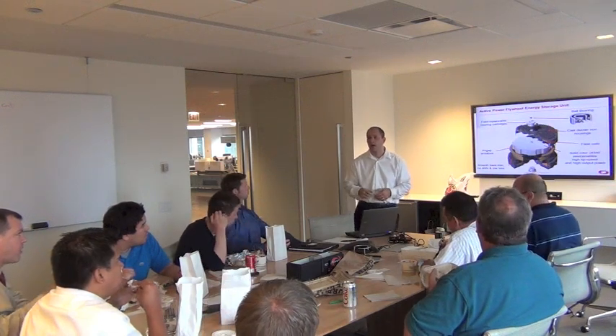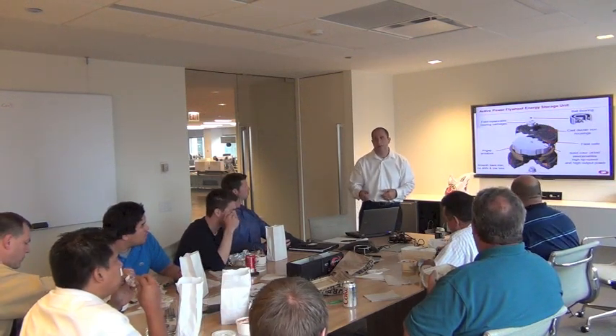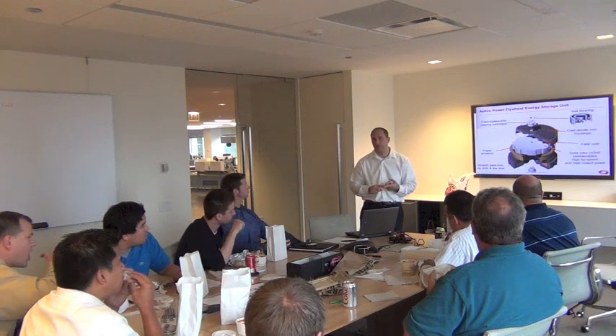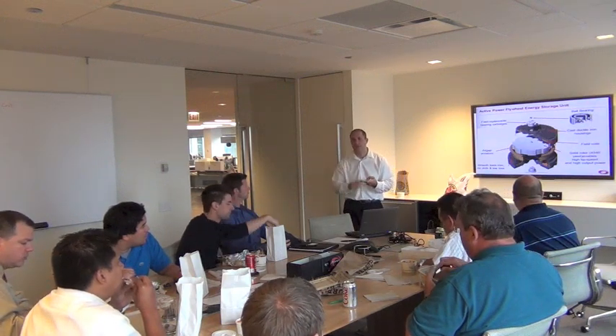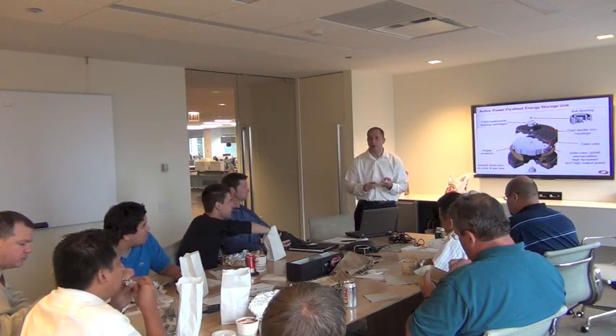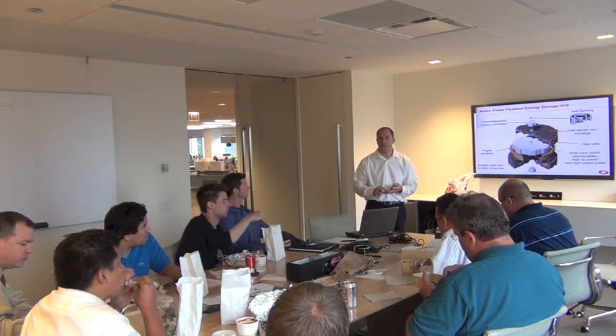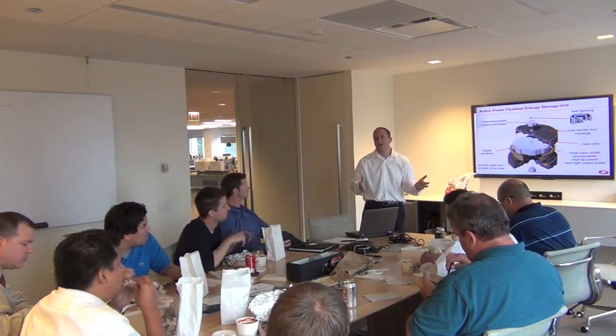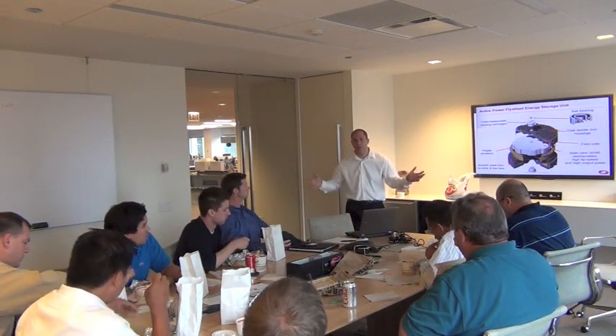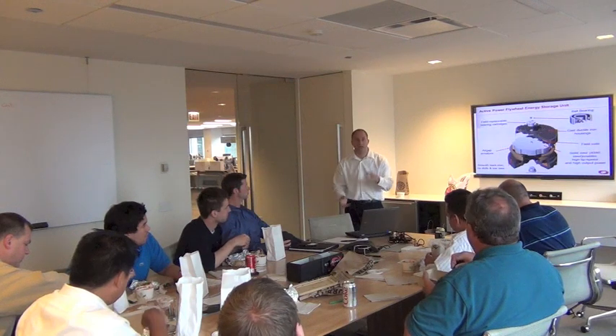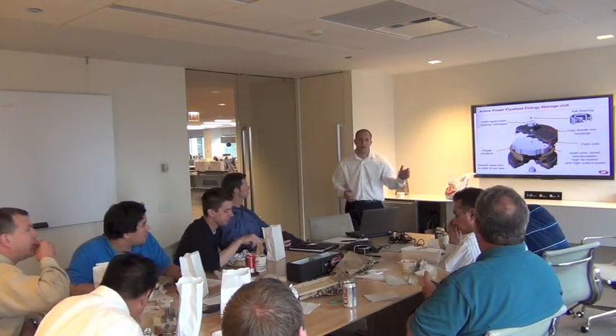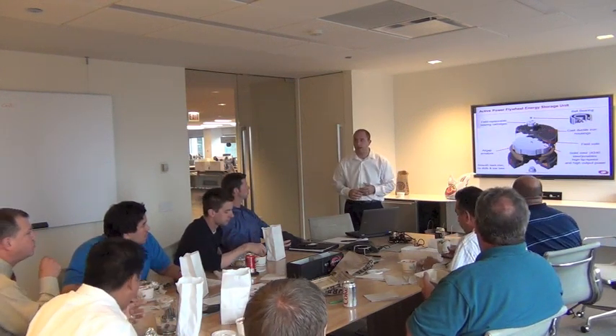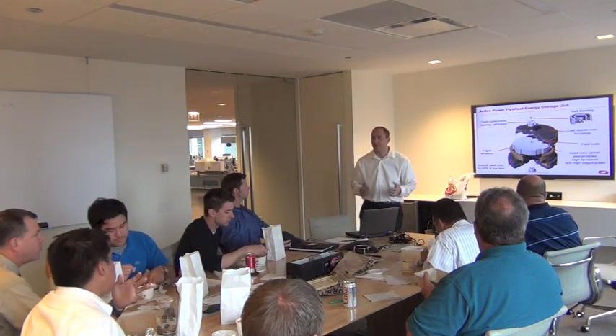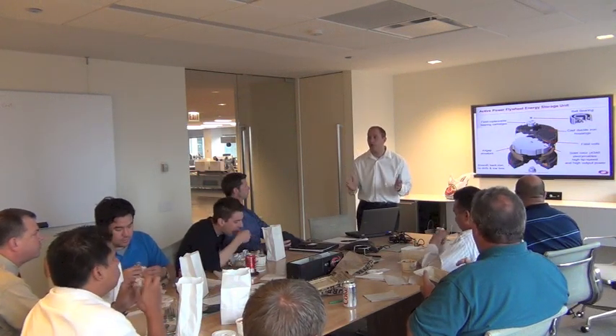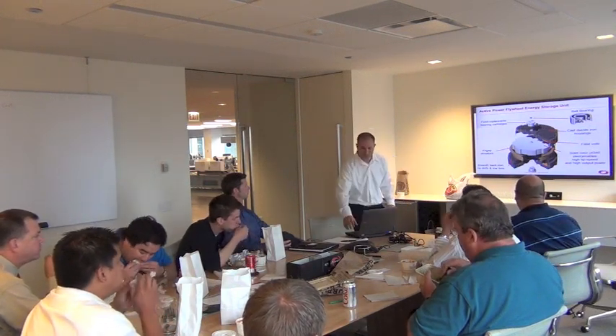You take the filters out. You can vacuum them out or clean them out or even wash them. Typically, that's just done once a year. So once a year, you'll clean the filters, change the mineral oil in the vacuum pump, and then once every 4 years, you'll change the bearings on the wheel. And when you have a multi-module installation or multiple wheels, you can isolate one wheel at a time, change the bearings, leave the other wheels online, protecting the load, and then move on to the next wheel. So you don't necessarily have to put the system in bypass for an annual maintenance or bearing change.